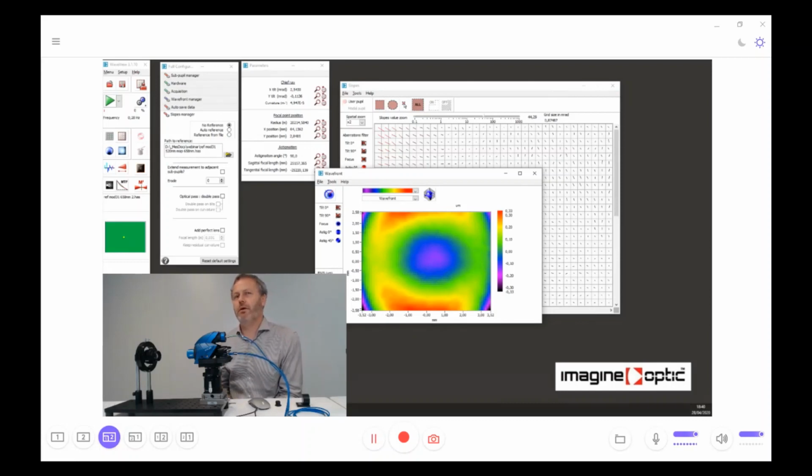Maybe nobody knows, but a few people know, that even piezo interferometers have quite a large amount of aberration on the output beam. The aberration we measured on a piezo interferometer had more than 1 lambda of aberration, because the technique of piezo interferometry does not need a perfect beam, because the fringes are created between the reference plane and the secondary wave. And that's the same here. Even if we have a small aberration at the output of the R-FLEX, it is subtracted by the reference.